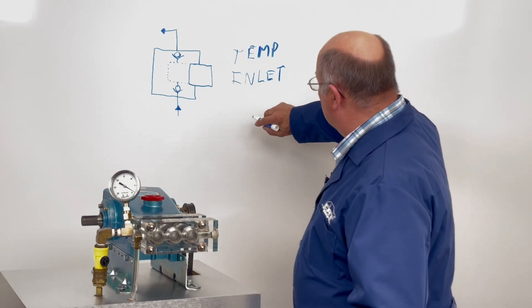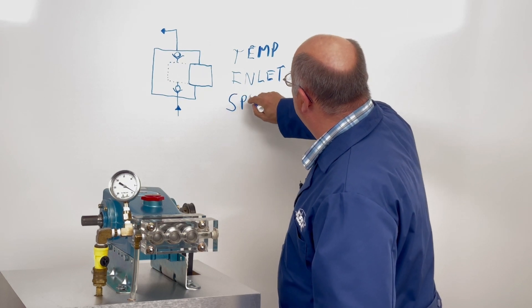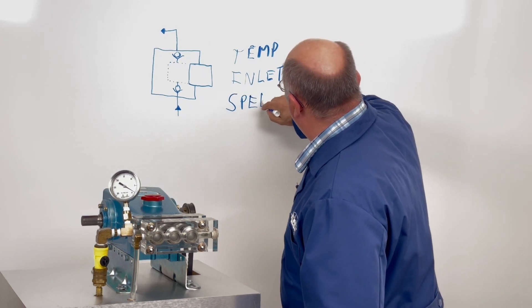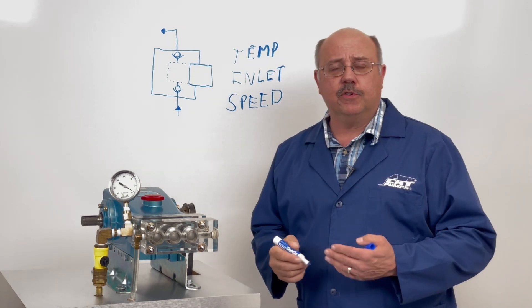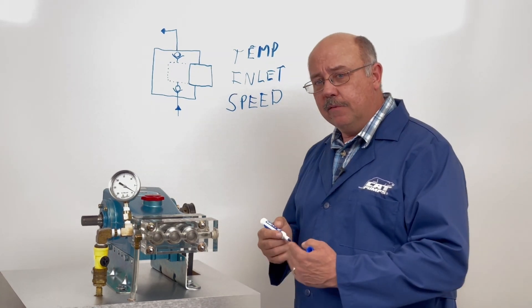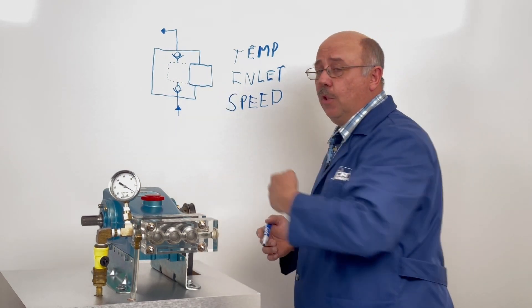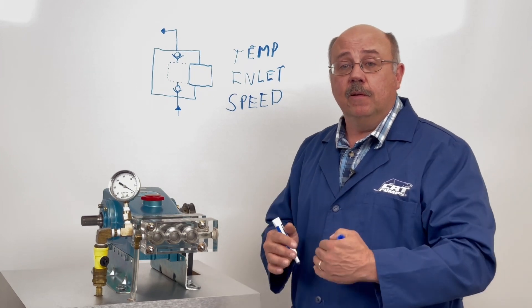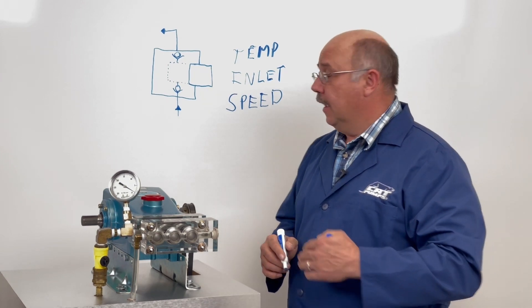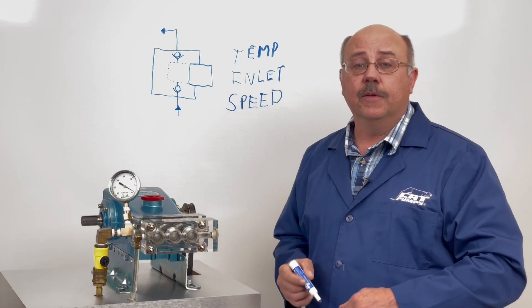The other thing we want to cover is the speed. The speed of the plunger refers to how fast the plungers are going back and forth or the RPM of the pump. If this plunger is moving very slow, it has a lot more time for each stroke to fill the chamber with water. If it's going very fast, it has a lot less time to fill during each stroke.